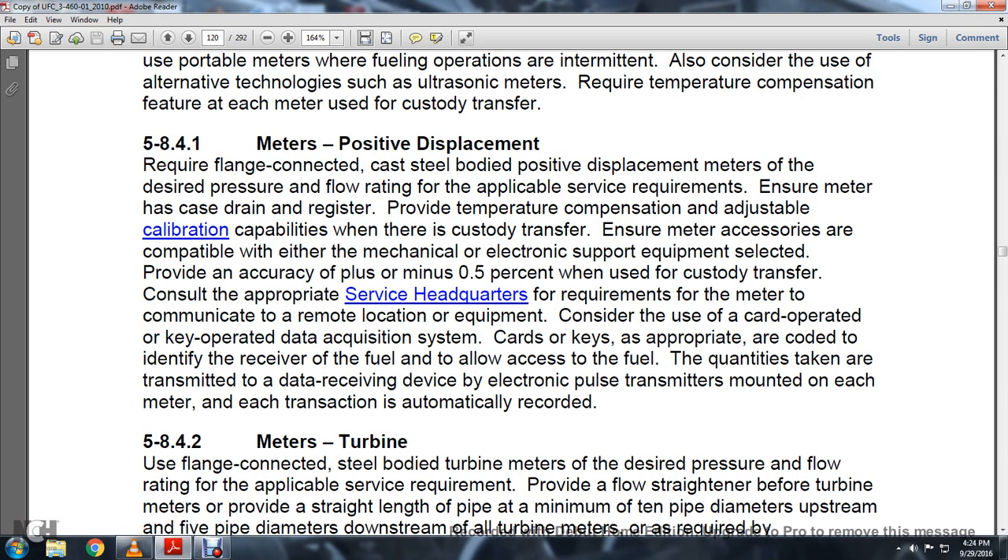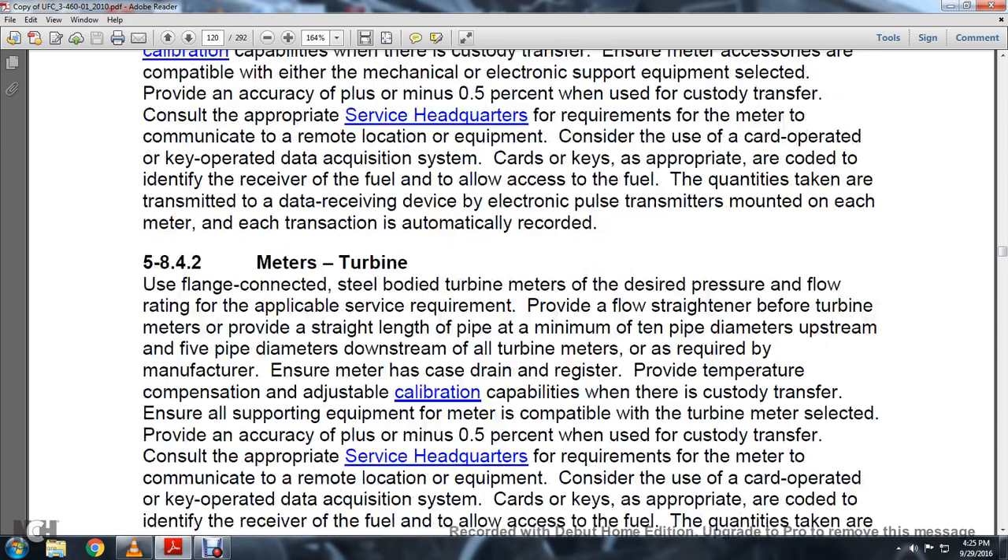Section 5.8.4.1 Positive Displacement Meters: Require flanged connections with a cast steel bodied. Size positive displacement meters to the desired pressure and flow rating of the applicable service requirement. Ensure the meter has a direct-drive register. Provide temperature compensation and adjustable calibration capabilities where there is a custody transfer. Equipment is selected and provided with an accuracy of plus or minus 0.5% when using custody transfer. Consider the use of card-operated or key-operated data acquisition systems to identify received fuel and allow access for recording fuel quantities. Each transaction is automatically recorded via an electronic pulse transmitter mounted on each meter.